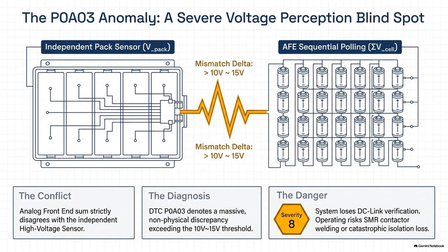Because of a parameter known as di/dt. That's the rate of change of current over time. Oh, right. Imagine that extreme dynamic load again. You stomp on the accelerator pedal. The motor inverter demands a massive influx of current instantly. The total pack voltage sensor, with its dedicated high-speed path, captures the resulting heavy voltage drop in real time. But the cell sensors are still sequentially polling down the line. They are 50 milliseconds behind the physical reality.